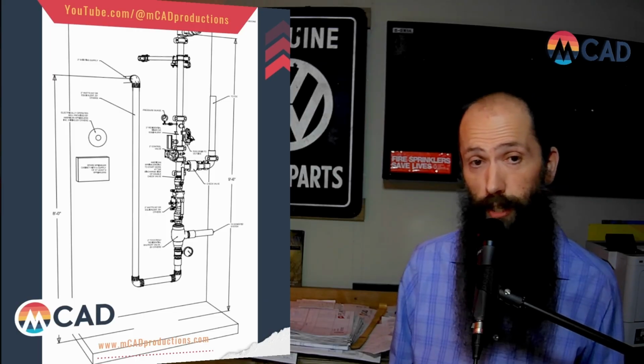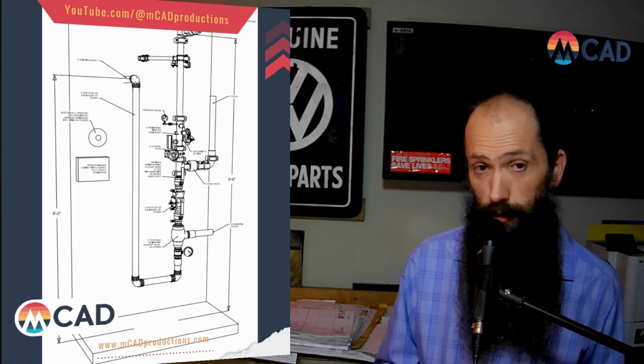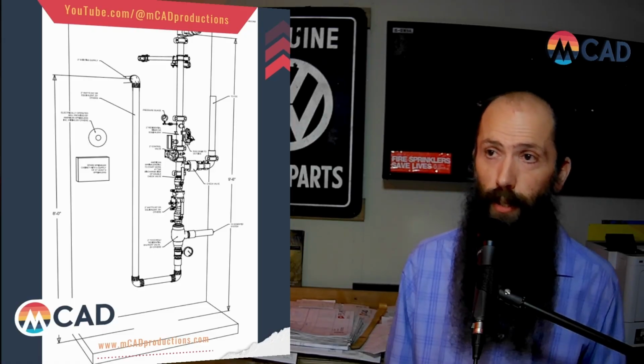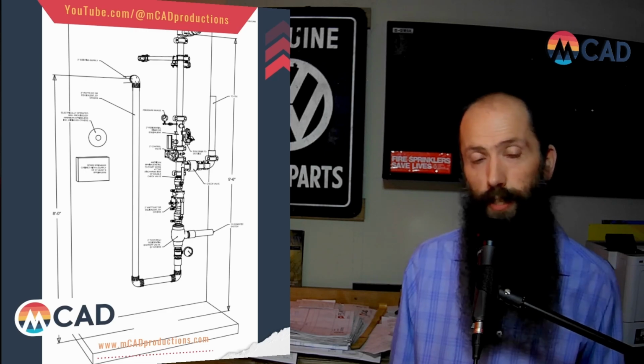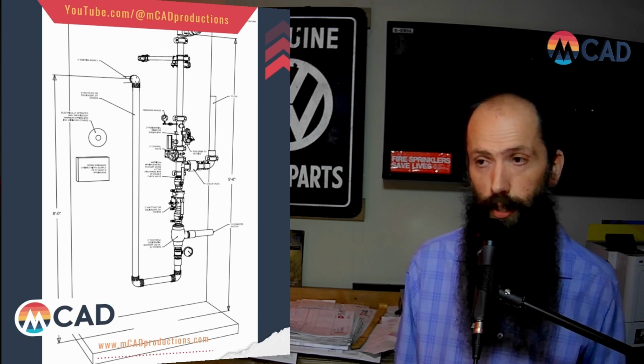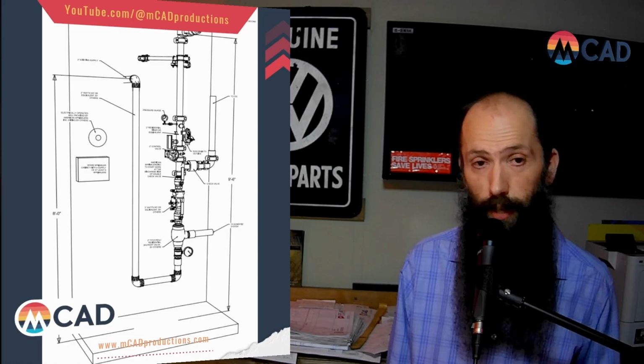Here is a riser detail from a project that started out as 13R, but they ended up having to do a full-on 13 system with standpipes. So initially, they tried to get it to work as a 13R with the plumber's supply. So we use an isolation valve from Tyco. And this is the valve that I'm talking about.